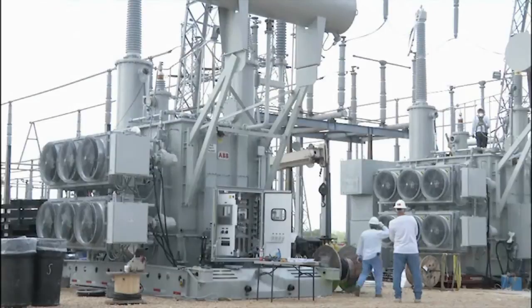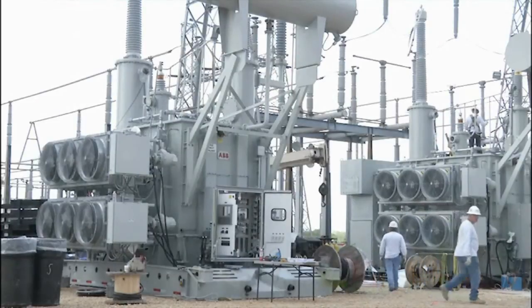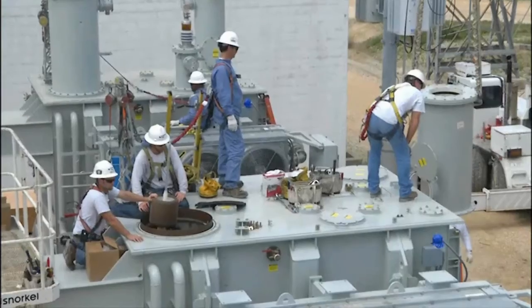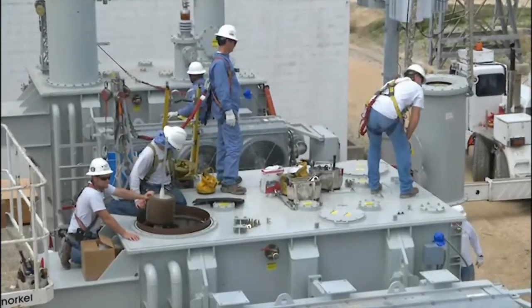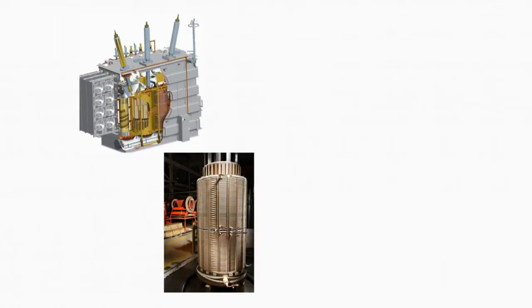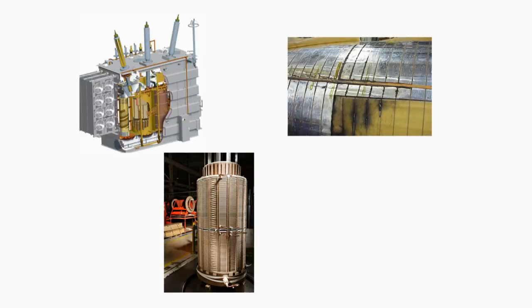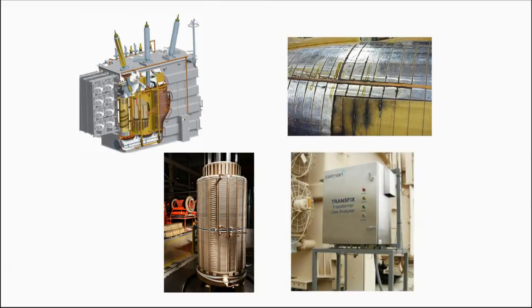The first demonstration centers on diagnosing degradation of the primary winding insulation, a common failure mode in a generator step-up transformer. When the transformer's primary winding insulation degrades, dissolved gases are created in the transformer's insulating oil. The type, concentrations, and ratios of gases are used to distinguish insulation degradation from other faults. Simulated faults were introduced into operating data, obtained from an in-service transformer equipped with an online gas analyzer.